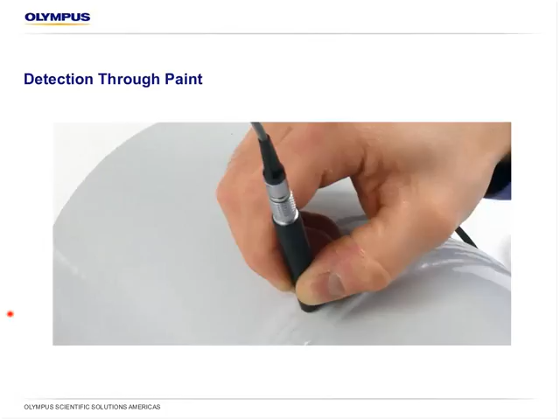So this first section is the first of the detailed explanations as to why this is an improved solution for carbon steel weld inspection. Detection through paint: basically, eddy current technology uses a magnetic field to couple the probe to the part being tested. The magnetic field can travel through air or through coatings such as paint - there's no difference for the magnetic field whether it's paint or air. The eddy current will work as long as the material being tested is conductive.